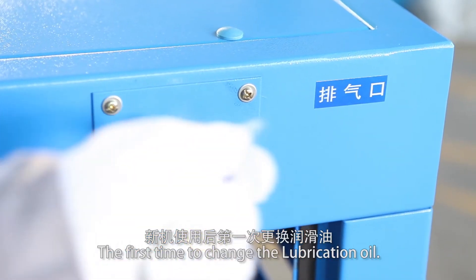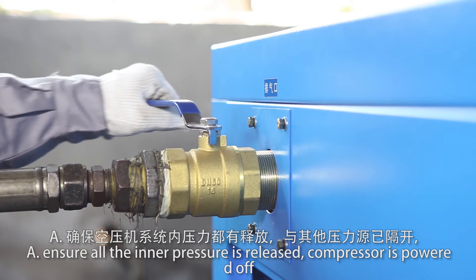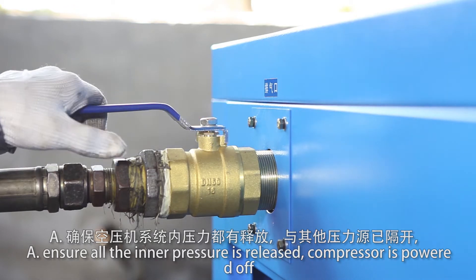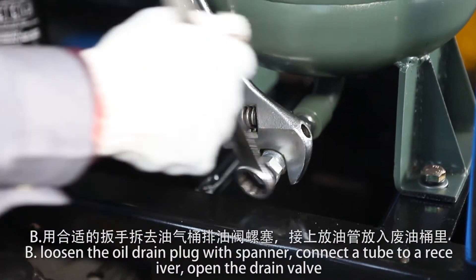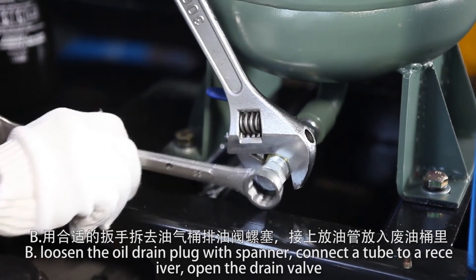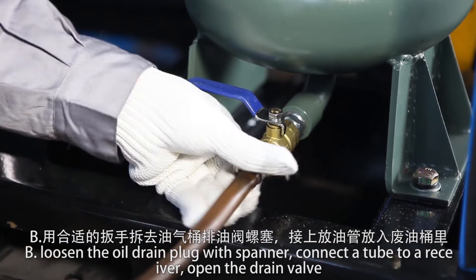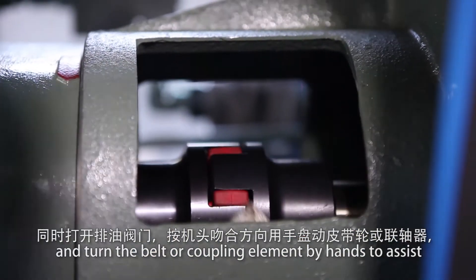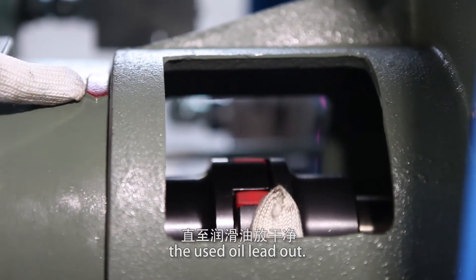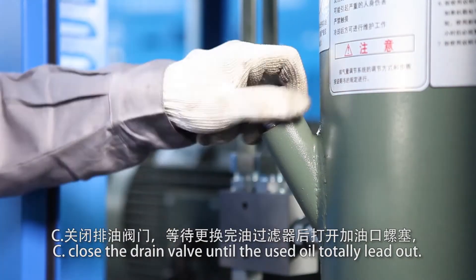The first time to change the lubrication oil: ensure all inner pressure is released and the compressor is powered off with a warning sign displayed before servicing. Loosen the oil drain plug with a spanner. Connect a tube to a receiver and open the drain valve. Loosen the drain valve and turn the belt or coupling element by hand to assist the used oil to flow out. Close the drain valve until the used oil has totally drained out.